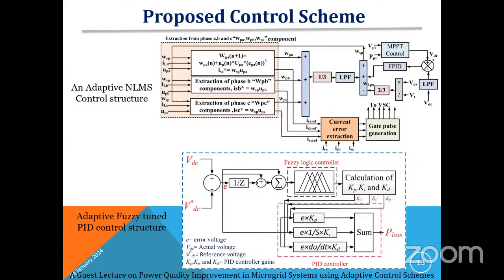So how much do we have to maintain? Roughly, we have to maintain 1.5 times the AC bus voltage. Suppose the AC bus voltage is 415, then 1.5 times 415 is approximately 650 to 700 volts that we have to maintain at the DC bus. Otherwise we can't send the maximum power from the renewable energy source to the utility grid, because we have several losses because of the high switching devices connected between the DC and AC sources.